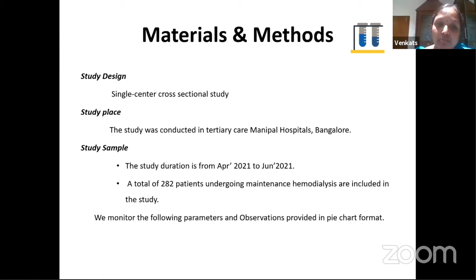Minimum 6 quality indicators. These are the 6 minimum quality indicators which have to be maintained in every individual dialysis setup, which is really mandatory for providing good quality dialysis to a patient. Coming to the first one, that is water quality, we do monthly samples for microbial count and endotoxin count. It is not just one sample, it depends on the unit size. If the unit is really big, we may require many samples which have to be sent for microbial growth. And then endotoxin samples, we make sure every machine is covered at least once in a year for endotoxin count or for dialysis fluid endotoxin analysis.